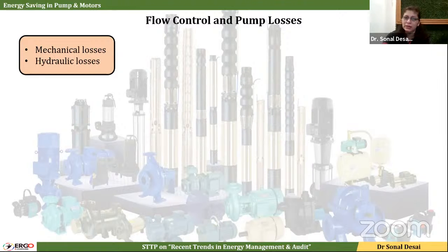I'm driving my car, I'm putting the accelerator as well as the brake together, and then ultimately I'm complaining that my car is not getting full average. Just like that, the same thing happens in a pump. Most of the cases, looking at the future need or the variation in the load, we design the pump in such a way that, compared to the present requirement, we go with a higher sizing. And ultimately, we need to control the flow because our present requirement is less and our present equipment is not able to handle more flow. So ultimately, we have to control the flow.